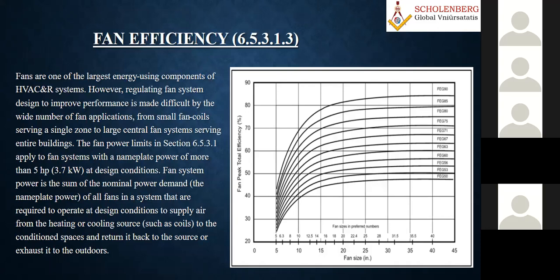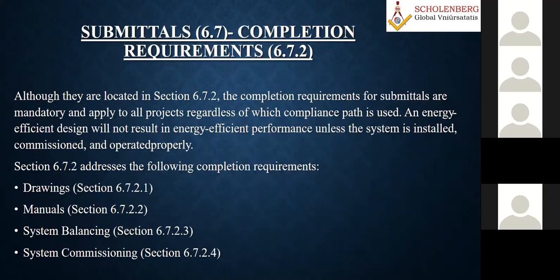And then in the fan efficiency section, they beautifully talk about how fan technology has advanced so much nowadays. Fans and blowers are a very specialized subject. It is nothing but mechanical engineering, like centrifugal pumps, except a fan handles air. Most of the time they are centrifugal blowers, which may be forward curved, backward curved or normal curved, but axial flow also has its own advantages and disadvantages. These are the fan efficiencies this section talks about, since it is 90.1, and these sections are given in that.